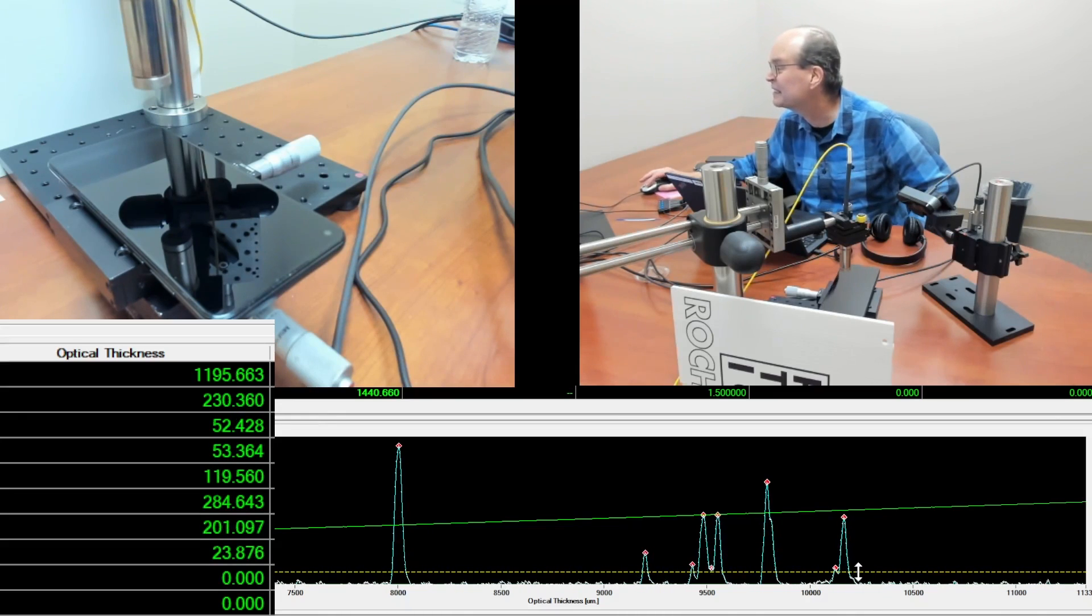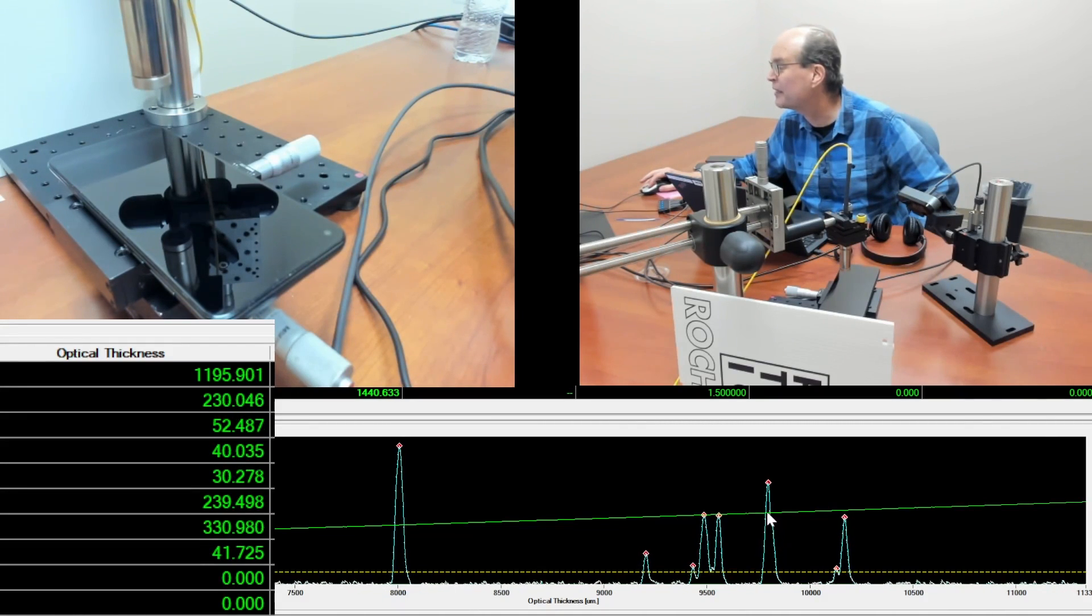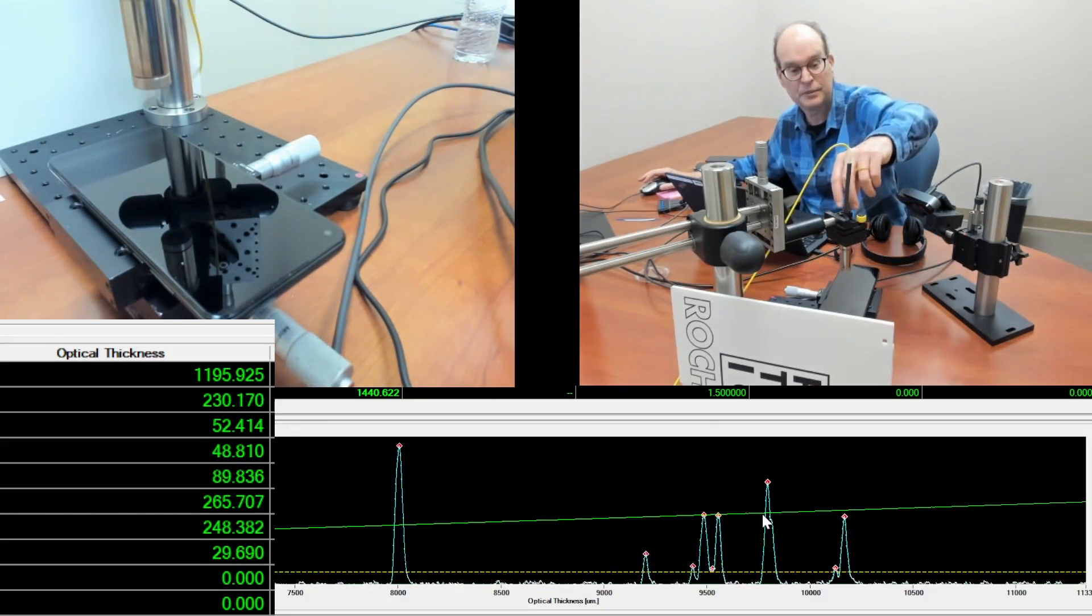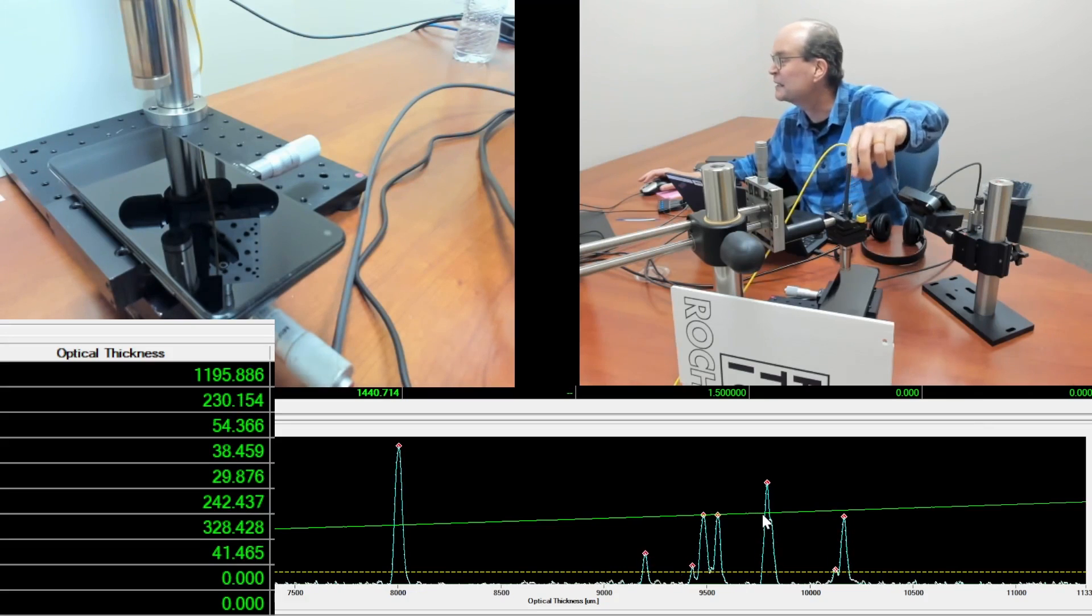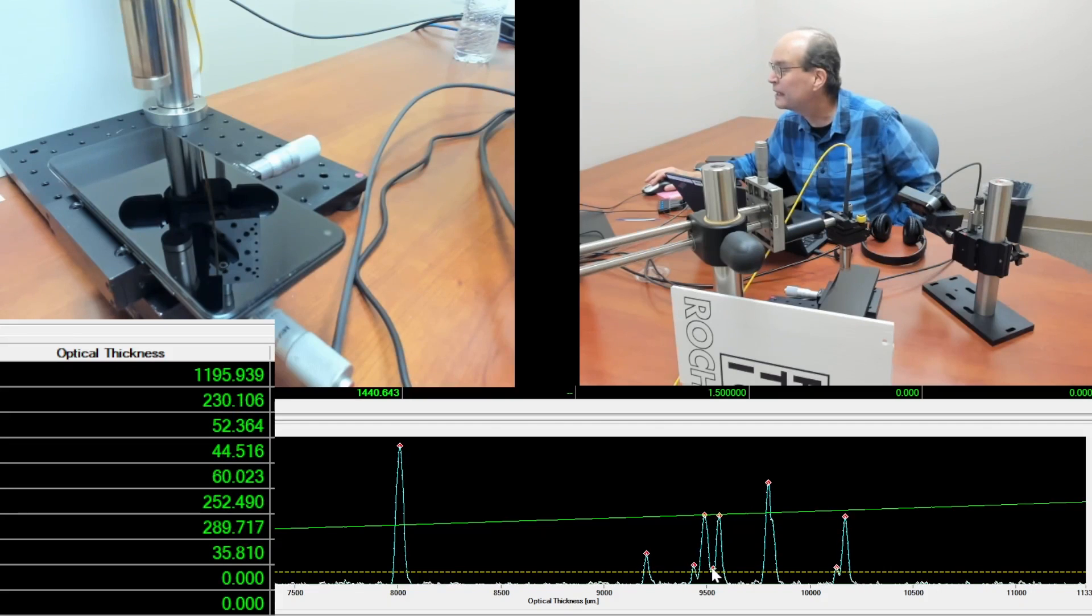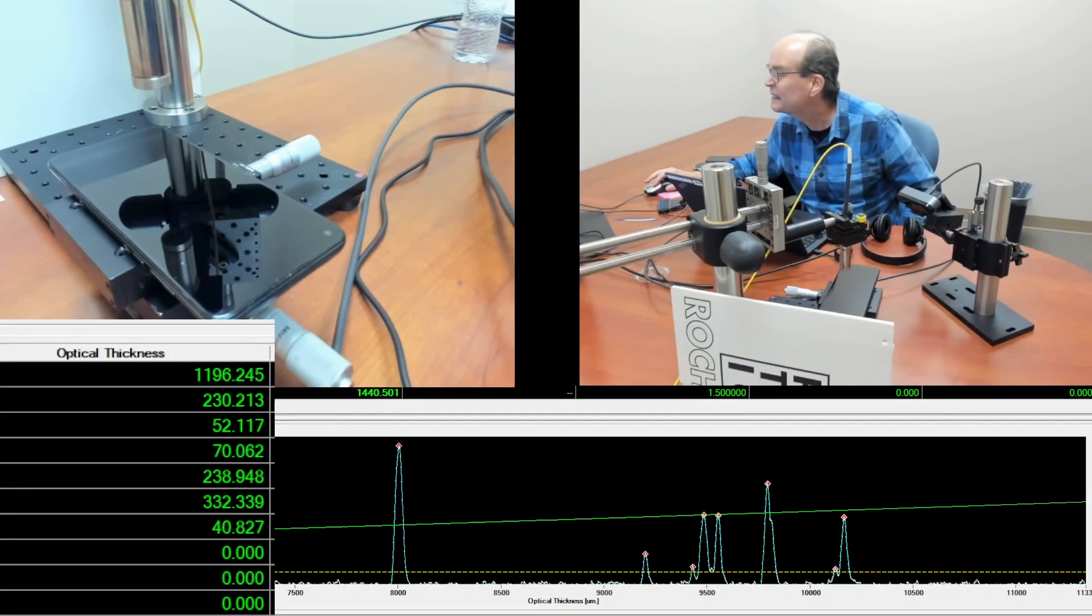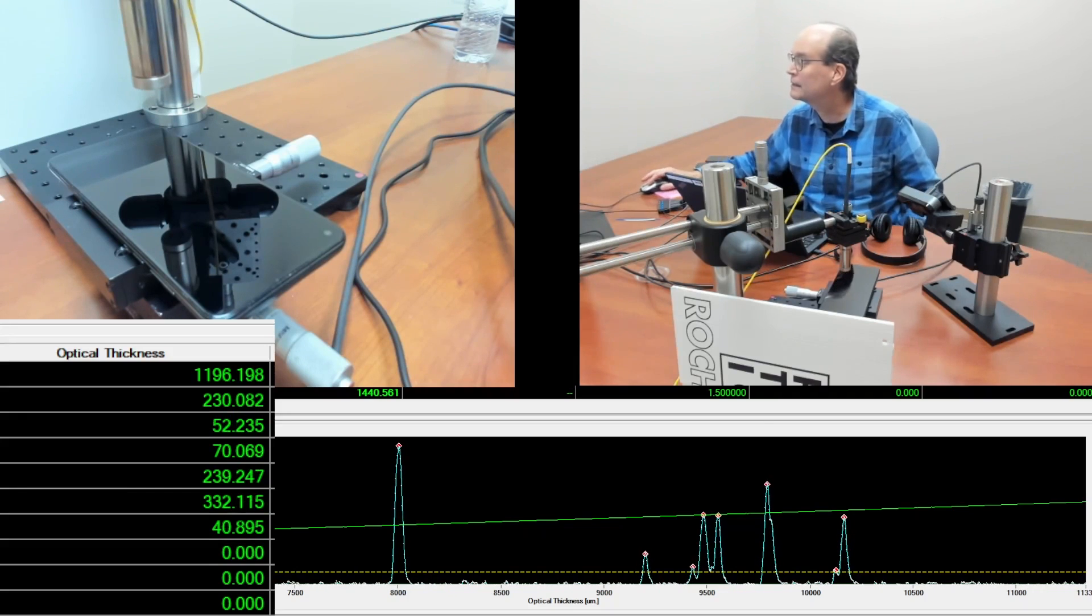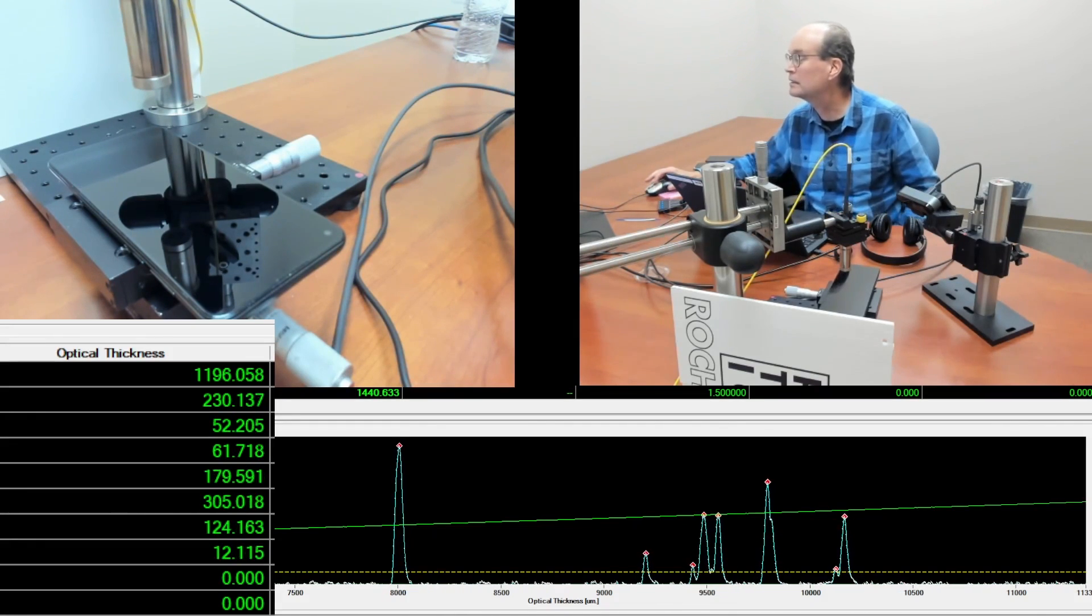It's hard to say if this little section here might or might not be a layer. That actually might be a layer, a thin layer in between. There could be two layers there. I'd have to fuss with the alignment a little. But I'm going to say that one, if it's there, it's hard for me to find. It might be below our thresholds of 12 microns. We do actually show a layer popping up in between there. Not until we went to nine peak width that this layer disappeared. So I'm going to go back down to the peak width of five and call it a layer.